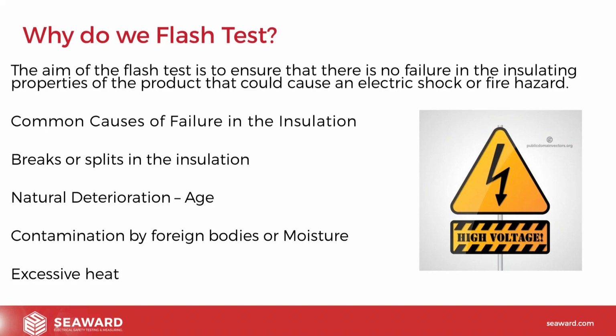Any contamination by foreign bodies. This could be particularly prevalent when using grinders. For example, we could get a buildup of conductive material within the unit. That conductive material could create a path to the exposed metalwork on the product that could potentially cause a shock hazard. And any kind of excessive heat. Heat again potentially will warp the insulation, potentially causing it to melt, exposing internal conductors, and therefore providing a risk hazard. So ultimately, we do the flash test to ensure there's no breakdown in the insulation, and that we're ultimately keeping our customers safe.